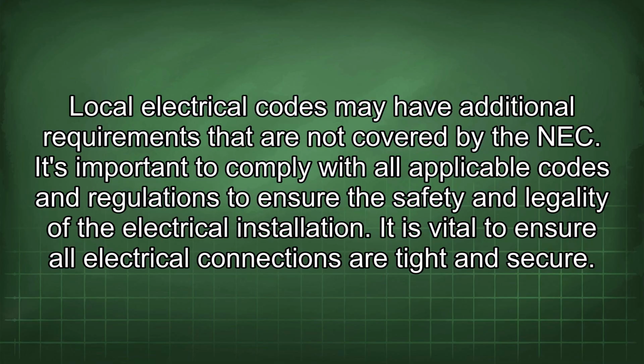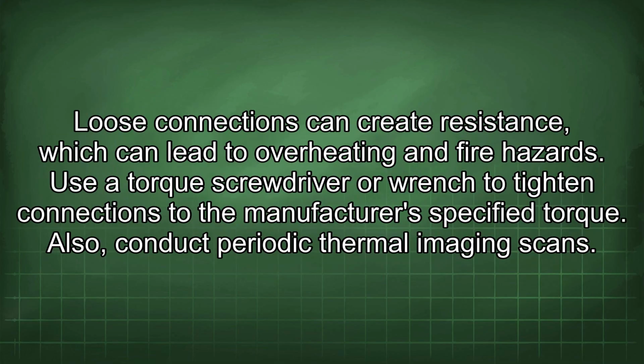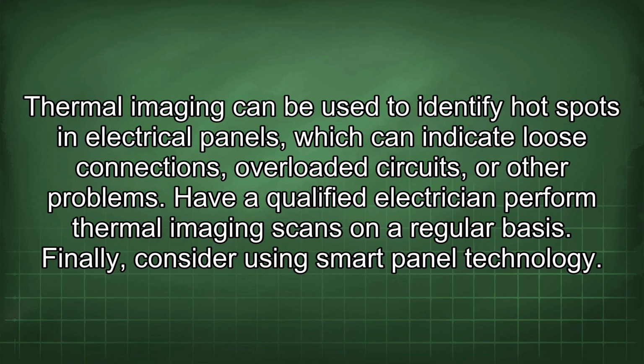It is vital to ensure all electrical connections are tight and secure. Loose connections can create resistance, which can lead to overheating and fire hazards. Use a torque screwdriver or wrench to tighten connections to the manufacturer's specified torque. Also, conduct periodic thermal imaging scans. Thermal imaging can be used to identify hot spots in electrical panels, which can indicate loose connections, overloaded circuits, or other problems. Have a qualified electrician perform thermal imaging scans on a regular basis.